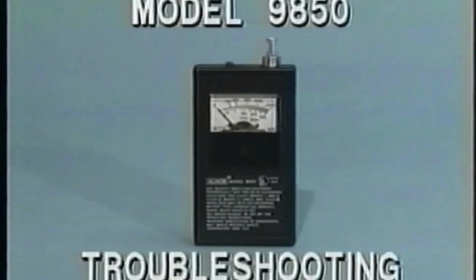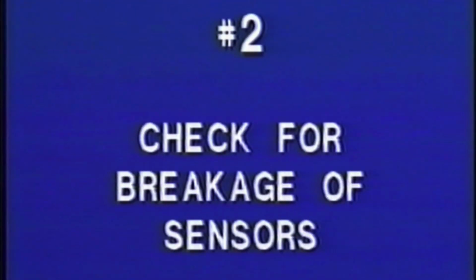In the unlikely event you should experience any difficulty with the operation of the 9850, the following performance check could be beneficial. Always start by verifying that the meter reads 0 both mechanically and electrically with the probe retracted into the case. Also check on the battery voltage by reading the meter when the unit is switched to the battery position. When using, if the needle is hitting against either barrier post or is moving erratically back and forth, turn off the instrument and check for breakage of the sensors in the probe.